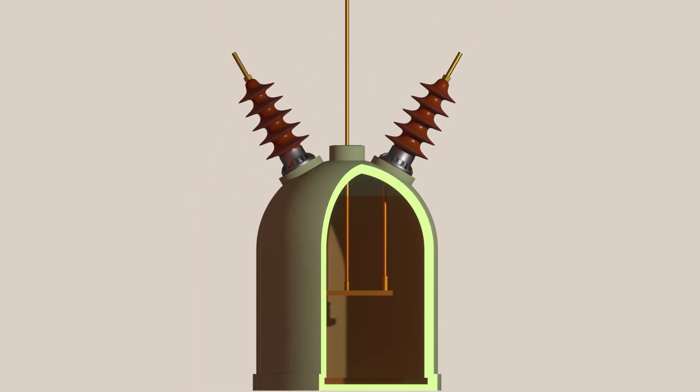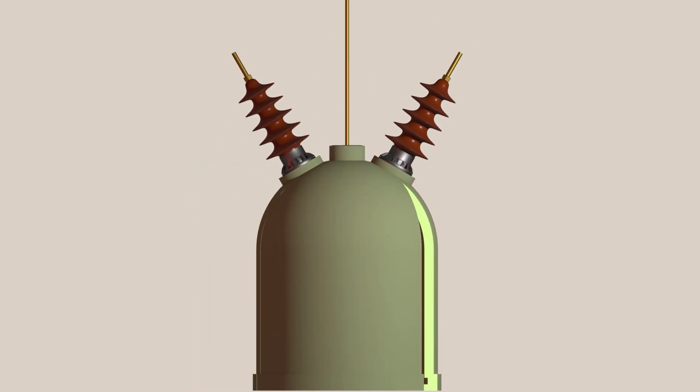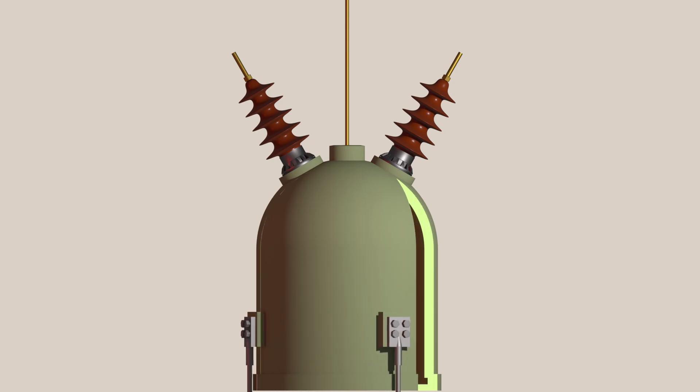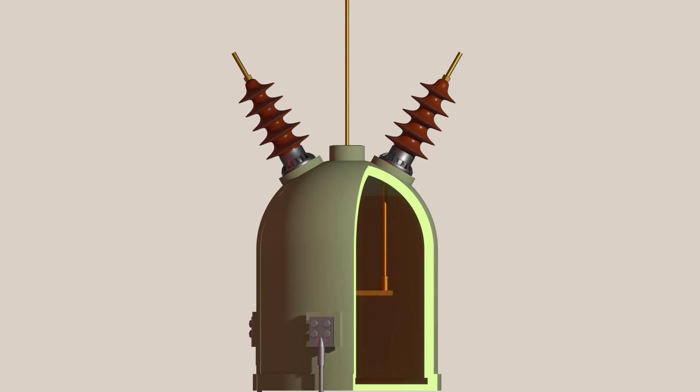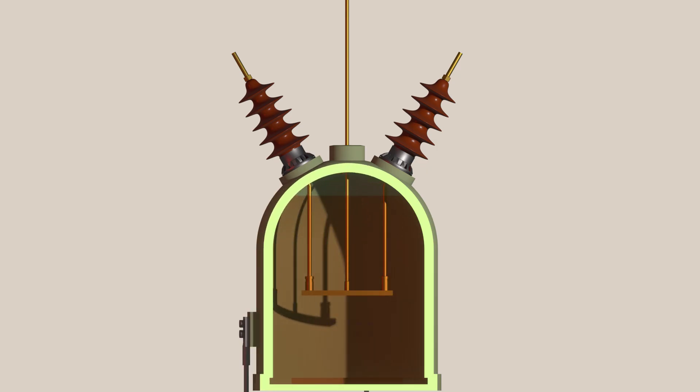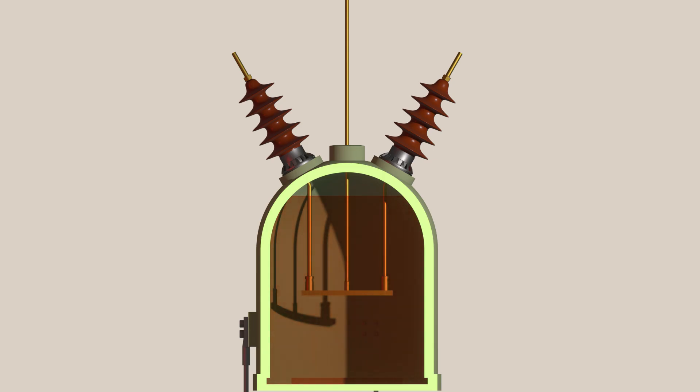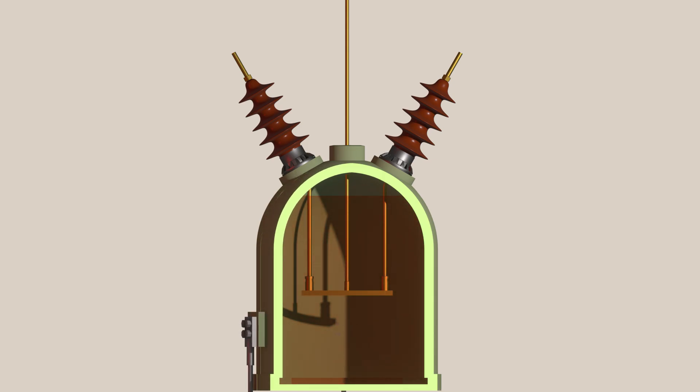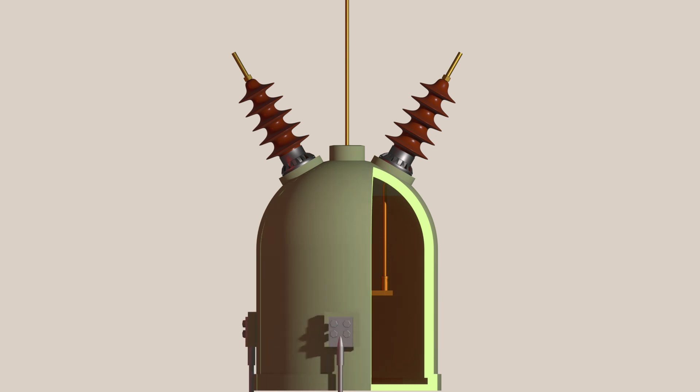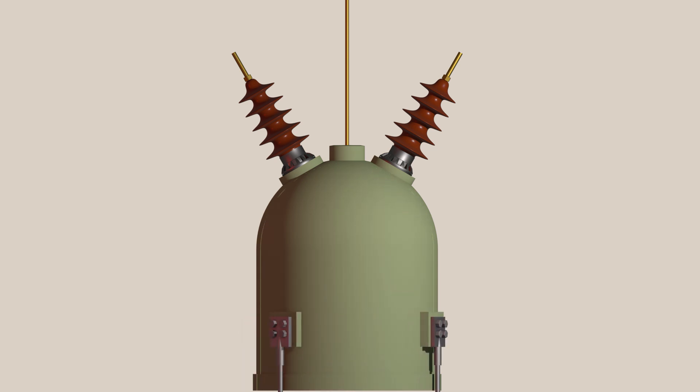The external tank, made of iron or steel, is directly connected to earth. The oil inside the tank provides necessary insulation between the tank and the live conductor. Since the body is earthed, it is a dead tank type design.